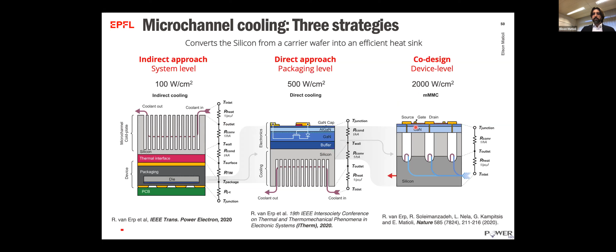And the ultimate approach would be what we call the co-design. It's basically one where we design the electronics and the cooling together. So we can now make these microfluidic channels in direct contact with the hotspot, and we can significantly reduce the thermal resistances that we see in these other two cases. And now we can cool down heat fluxes up to 2 kilowatts per centimeter square, extremely large heat fluxes. So let me show this approach here in this talk.